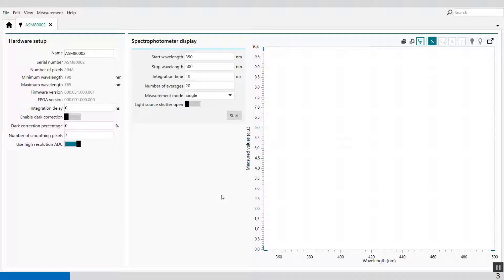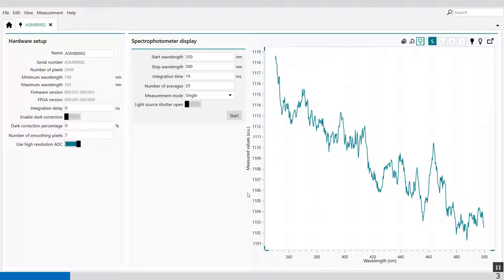First what I have to do is take a dark spectrum. I've connected the cuvette holder to the spectrophotometer and detector. I put a cuvette with just water inside and take a spectrum in the dark. I switch my light off, the shutter is closed, and I take a spectrum. The y-axis is in arbitrary value units (AU) and on the x-axis you'll see the wavelengths in nanometers. We can save this as a dark spectrum — save spectrum as dark. Select the dark light bulb icon, and now it's saved.